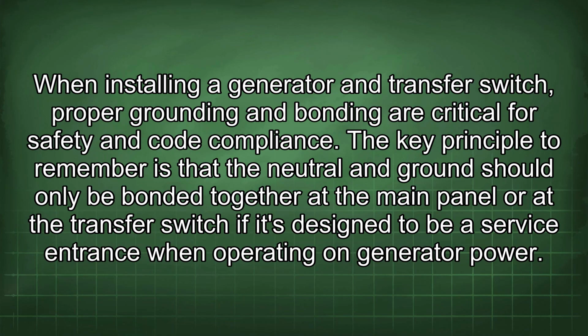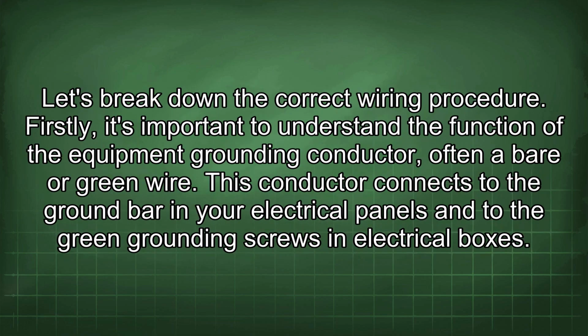When installing a generator and transfer switch, proper grounding and bonding are critical for safety and code compliance. The key principle to remember is that the neutral and ground should only be bonded together at the main panel or at the transfer switch if it's designed to be a service entrance when operating on generator power. Let's break down the correct wiring procedure.